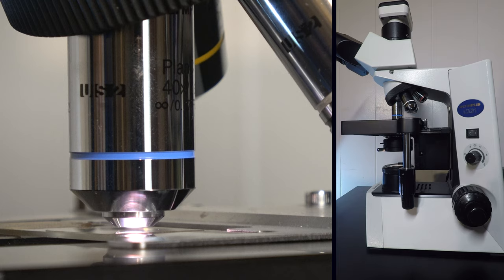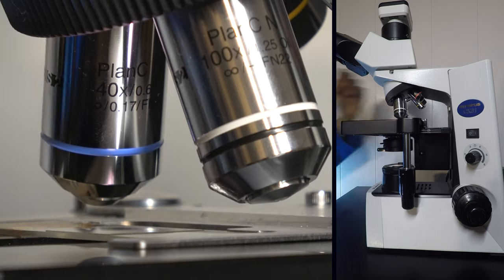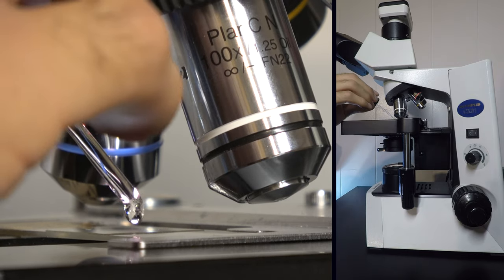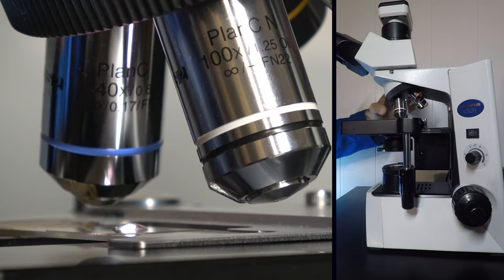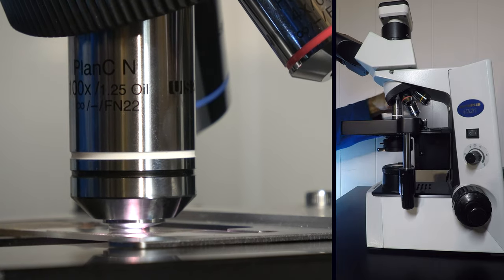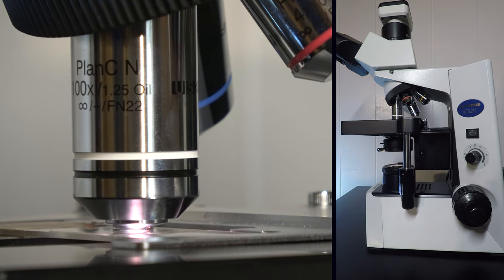Let's go back to the 40x. When transitioning to the 100x, move the turret halfway between objectives, carefully place a drop of immersion oil on the slide directly where the objective lens will sit, make sure there are no bubbles in the oil droplet, and slowly rotate the objective into place.